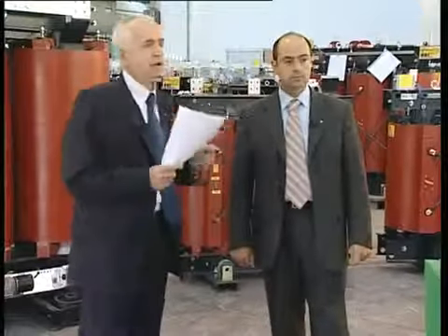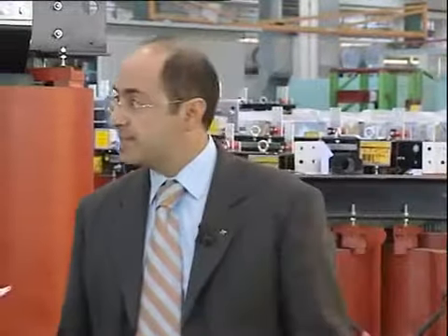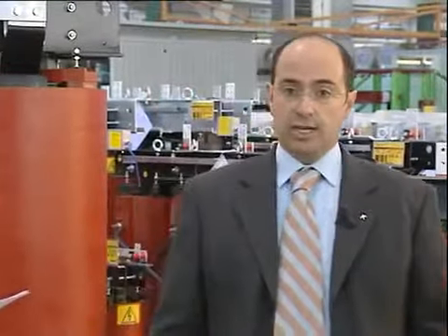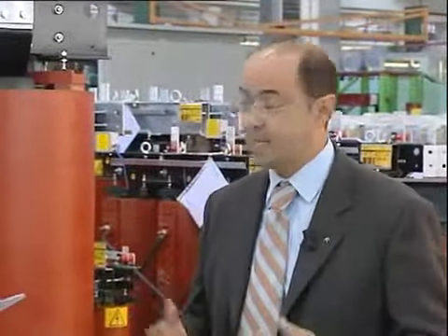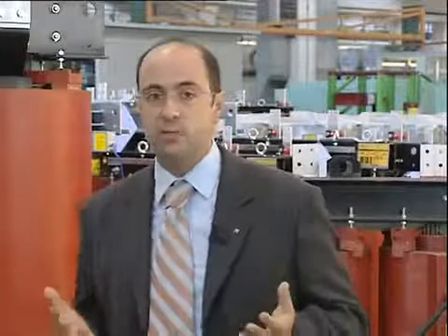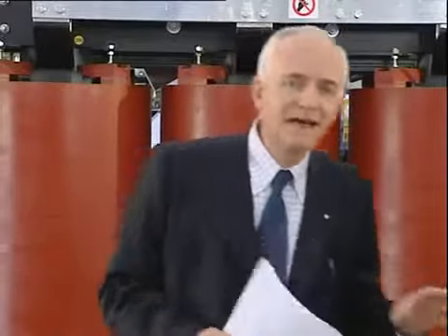Another question I have for you is the following. Can we find a generally even quality on the resin-insulated low-medium voltage transformers market, or, as you mentioned, are there considerable differences? Unfortunately, I must say that there are often unpleasant surprises. Transformers manufactured in a questionable way do exist, and this is one of the aspects leading some operators in the electricity sector to wrongly conclude that an oil-insulated transformer is more reliable than a resin-insulated one, while the opposite is actually true.